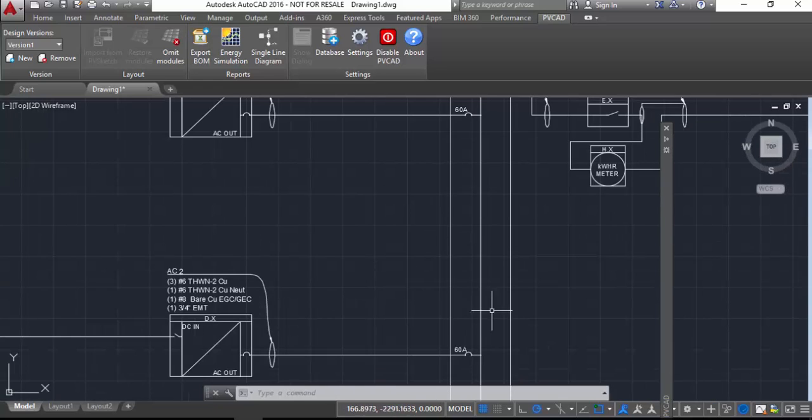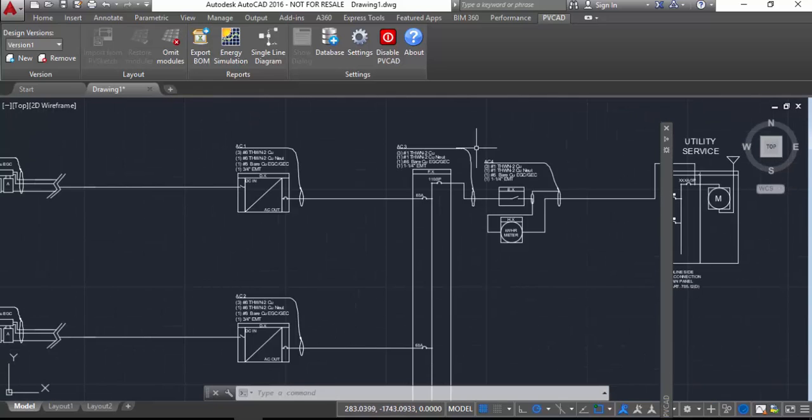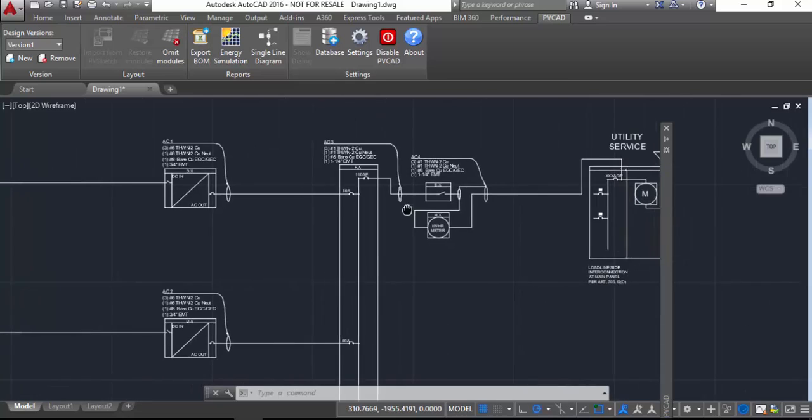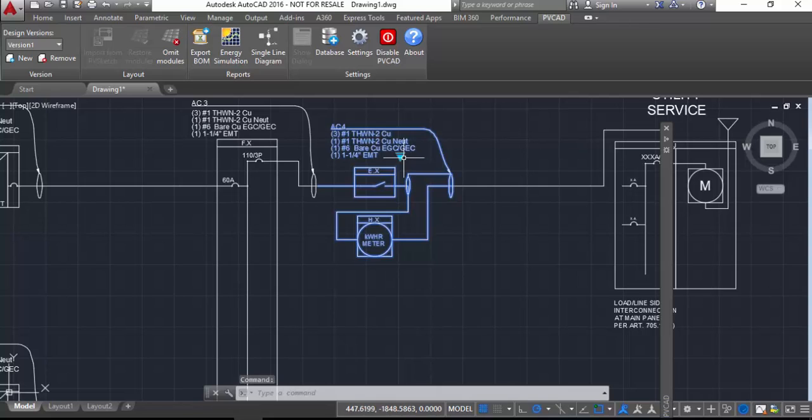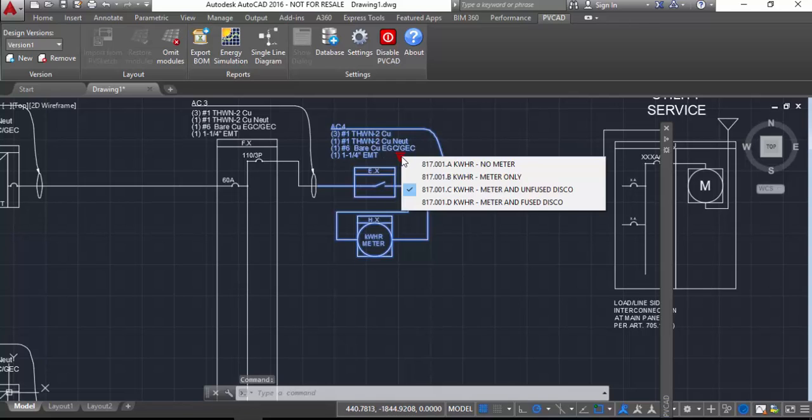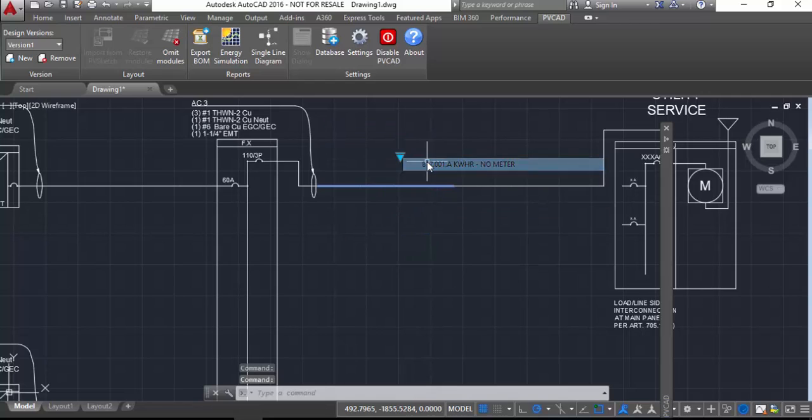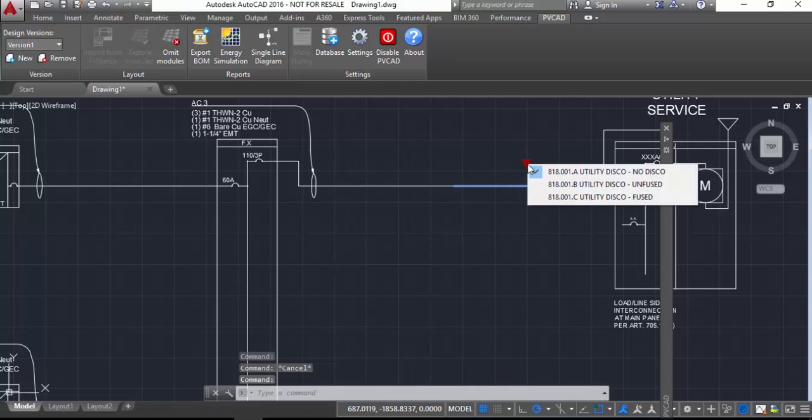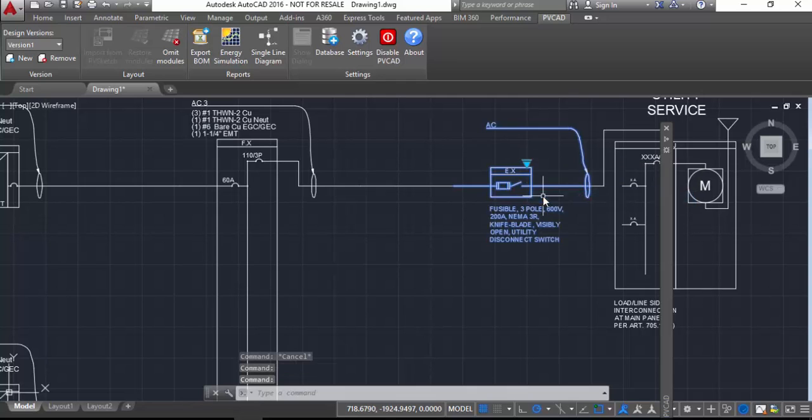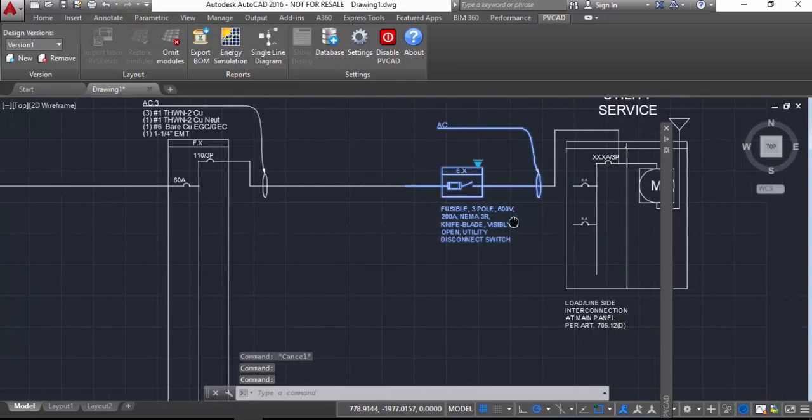And in general we have a lot of visibility states in the single line drawing blocks. So if I want to, I can actually do things like if I want to modify this meter block, I can get rid of the meter by saying no meter as my visibility state. If I want to add a disconnect switch, hidden in this block is both the unfused and fused disconnect switch options.